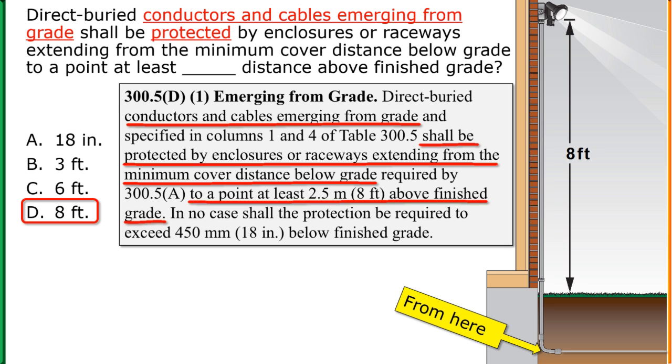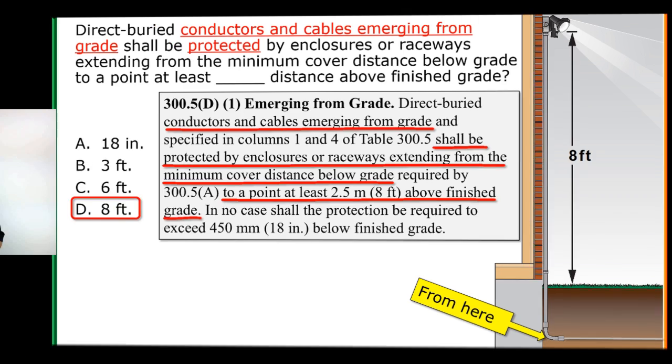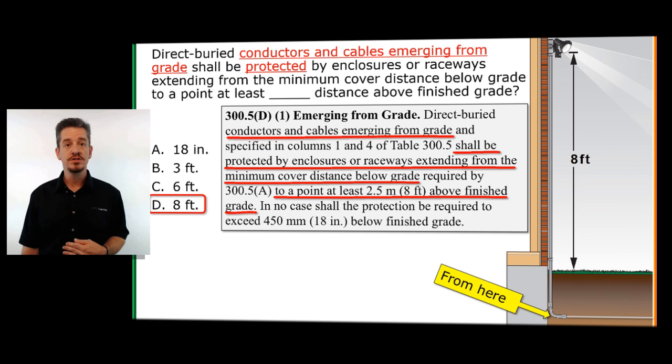Now look at the very last sentence. In no case shall the protection be required to exceed 18 inches below grade. So what that means is this: if your cable is required to be buried 24 inches deep according to the table, that raceway only has to extend 18 inches deep.